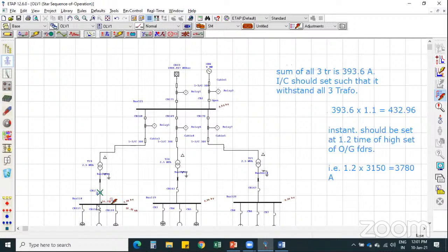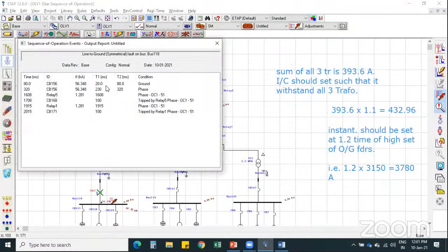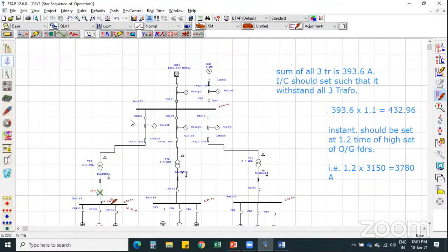So this is the sequence of operation. Likewise to both the relays, if ground fault protection fails to operate here, then the phase operation will be in a manner, we can see. Okay, see, in 80 milliseconds the ground fault operates first, and if it fails, then the phase overcurrent will operate at 320 milliseconds, and then this relay will operate if the circuit breaker fails to operate for this line to ground fault protection.